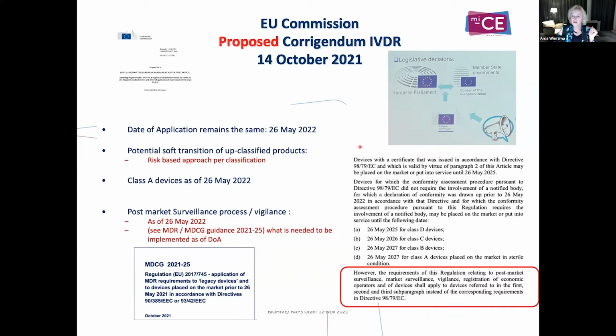However, they propose adjustments in the text, and you see here the most important ones. There is a potential soft transition for the up-classified products, and that's a risk-based approach per classification. So they included now here that for devices for which a conformity assessment procedure did not require a notified body, you have to get your CE certificate, your conformity assessment, for the Class Ds, the highest risk class, before 26th of May 2025. The Class Cs now have 26th of May 2026, and the Class Bs 2027.